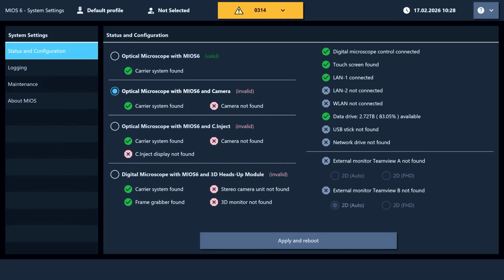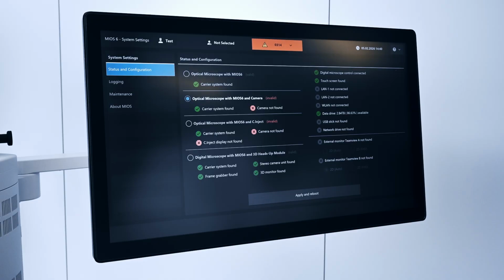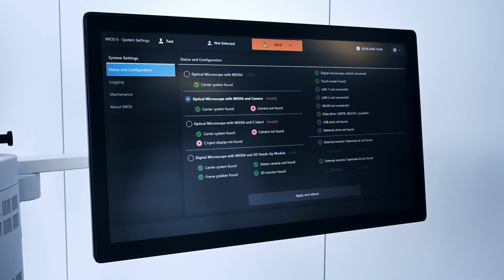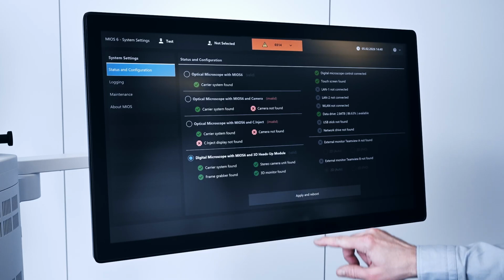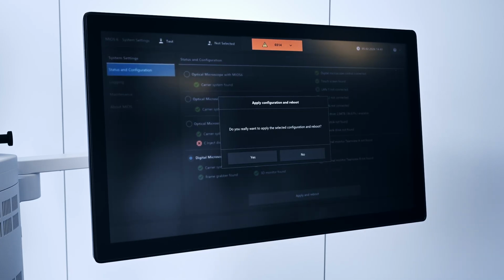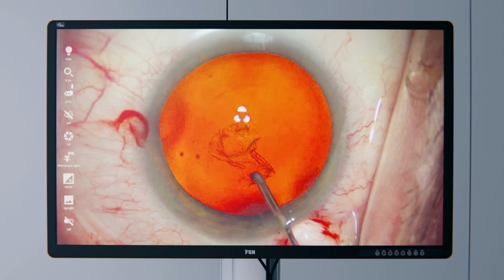If this is not the case, check that the cable connections are properly attached as explained in the previous steps. Now activate the configuration. The microscope's Configuration Check warning message at the top of the screen will disappear in the next step. Click the digital microscope with MIOS 6 and 3D Heads-Up Module button, followed by Apply and Reboot, and Confirm. Now, reboot your METIS Heads-Up. After rebooting, the digital microscopy image will appear on the 3D monitor.